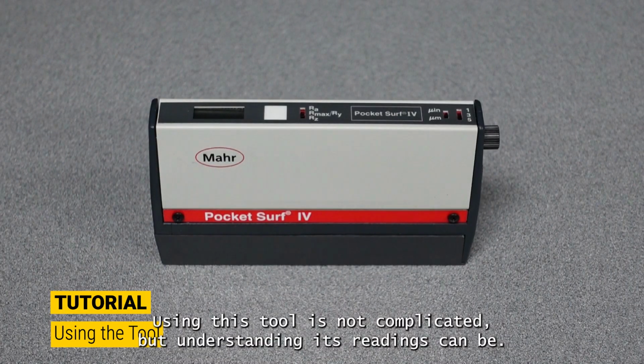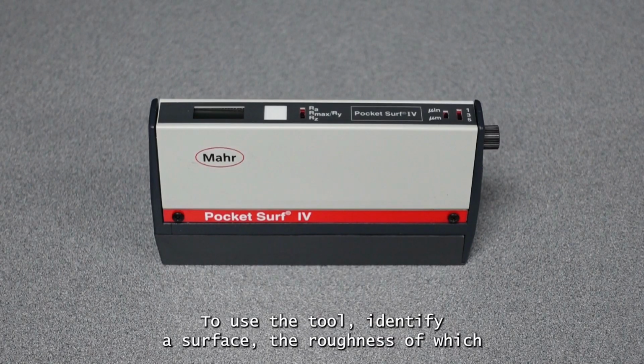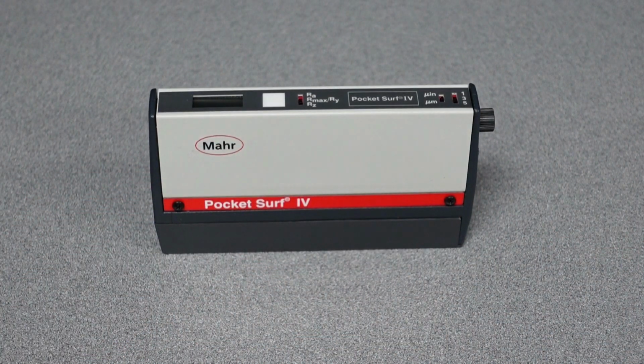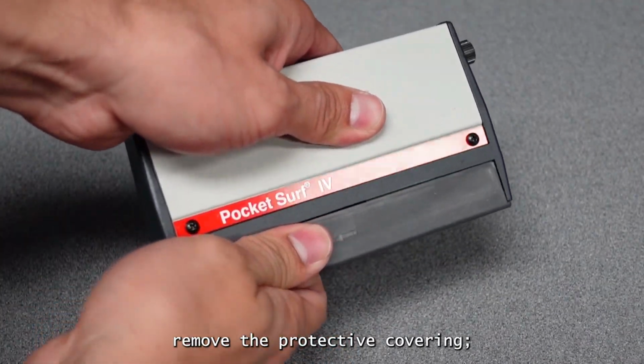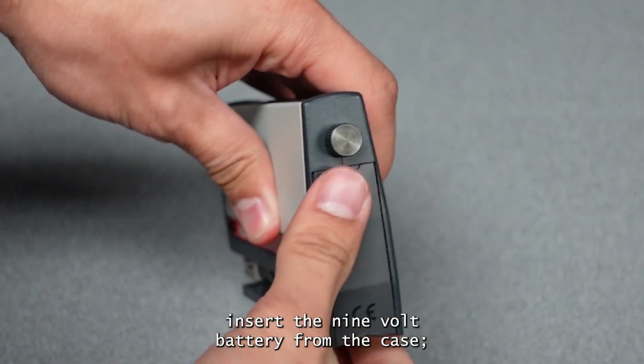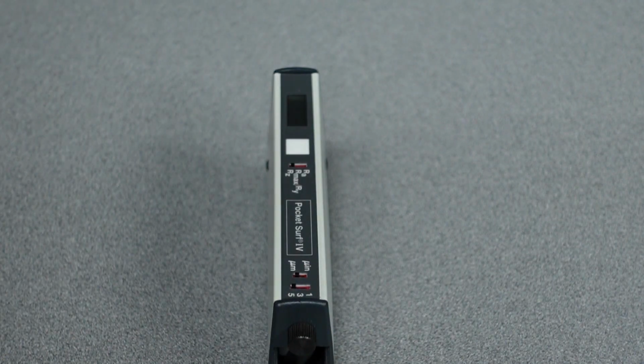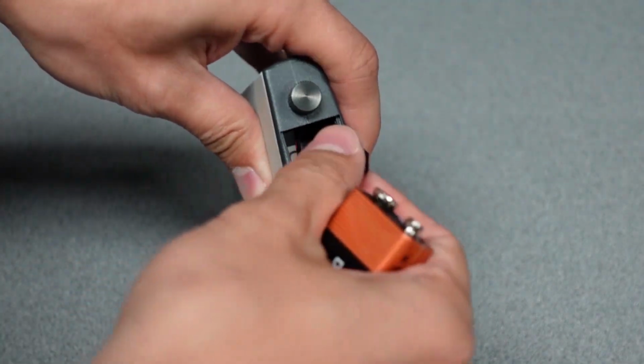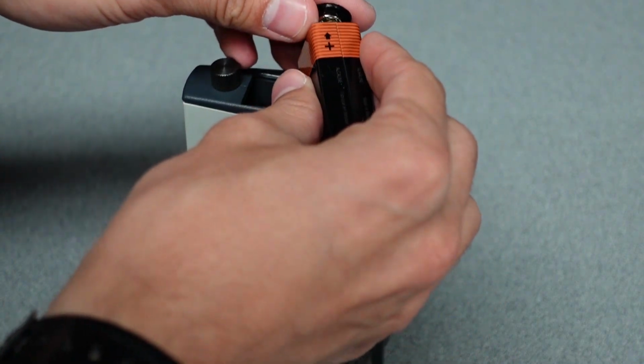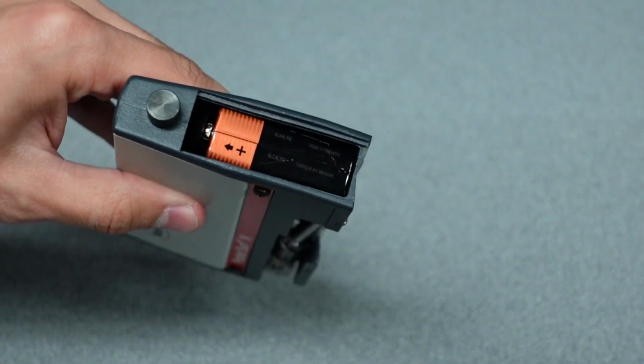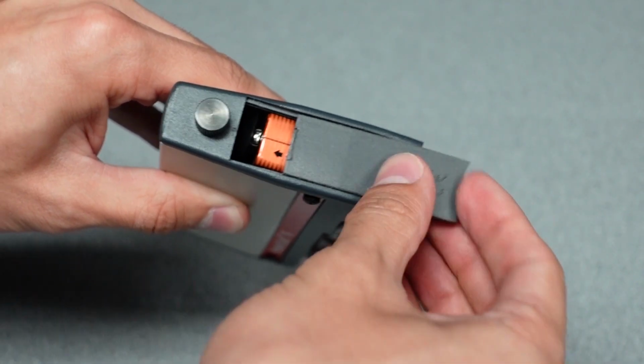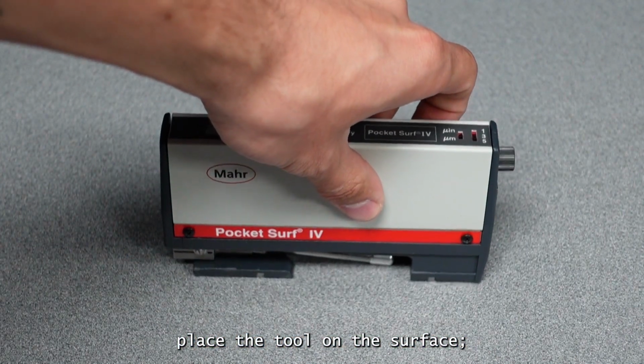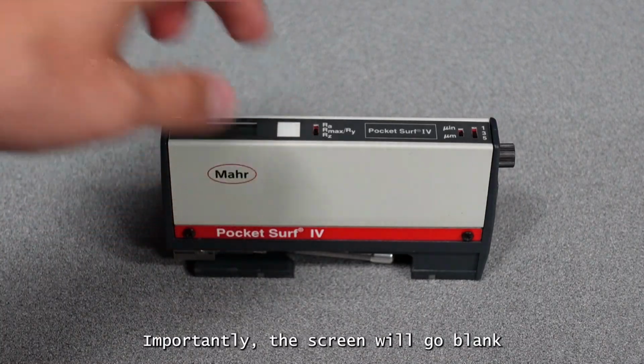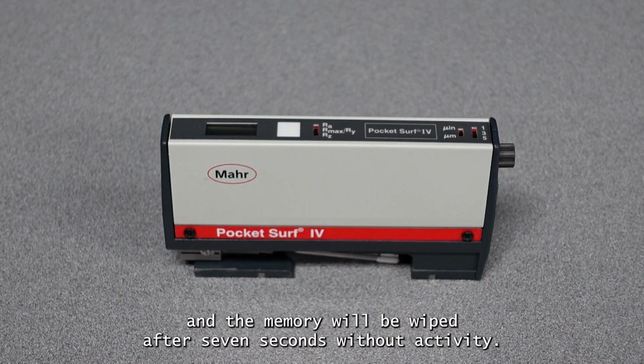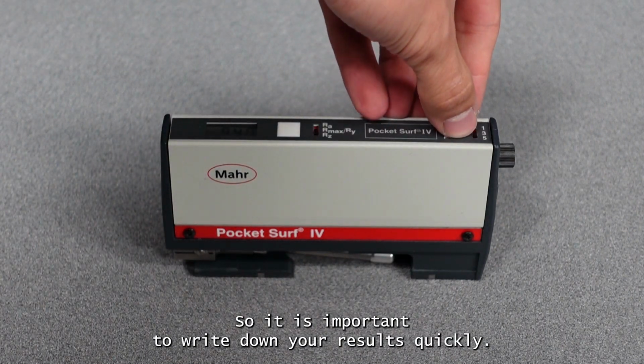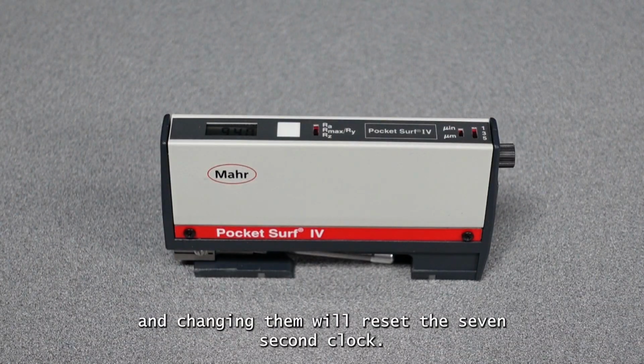Using this tool is not complicated, but understanding its readings can be. To use the tool, identify a surface the roughness of which you would like to measure. Remove the protective covering. Insert the 9-volt battery from the case. Place the tool on the surface and press the white button. Importantly, the screen will go blank and the memory will be wiped after 7 seconds without activity, so it is important to write down your results quickly. The units may be changed after taking the measurement, and changing them will reset the 7-second clock.